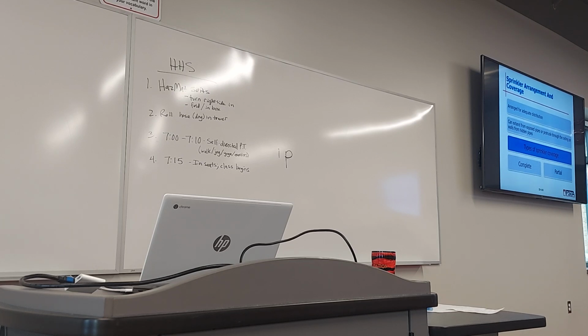So this is the spacing for sprinkler heads in a moderate hazard building use. If we decided to change this and store flammable liquids, tires, WD-40, oil, gas-oil mix, making it a maintenance area, this would no longer be the correct system to cover that hazard—that's now an extra hazard, and it needs closer spacing of the sprinkler heads.